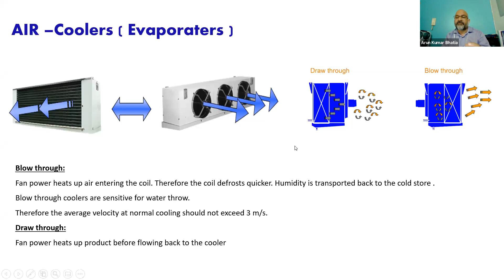Now we have a good cold store - everything is excellent, our compressor is good, our evaporator is good. But sometimes we make mistakes; we are not God. We sometimes lose track of our basics. So we have a good evaporator, good everything, but we are not placing the evaporator correctly. For example, if we have a beam here, the evaporator air will not reach the last end.